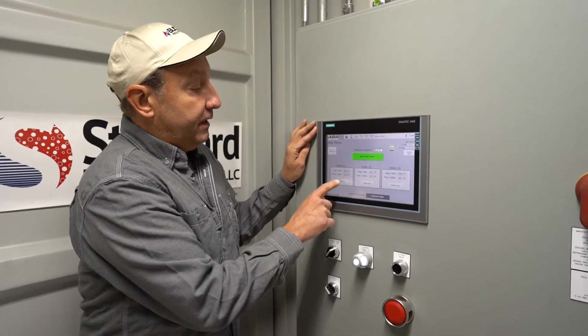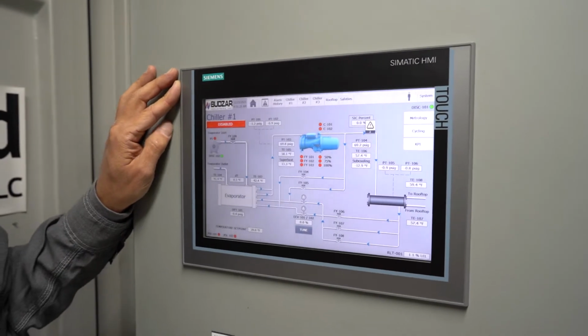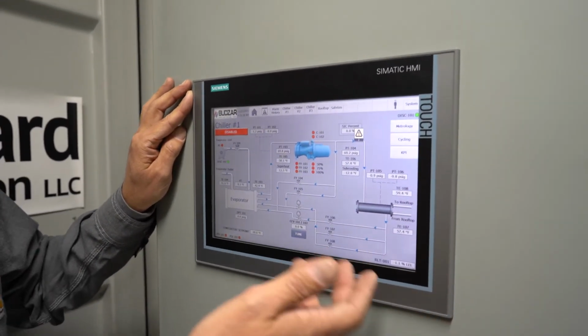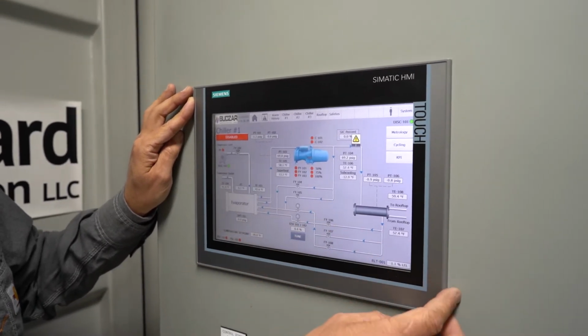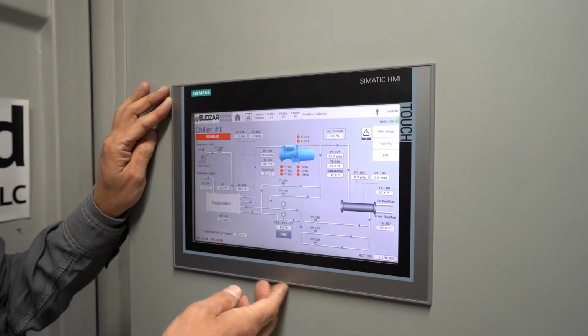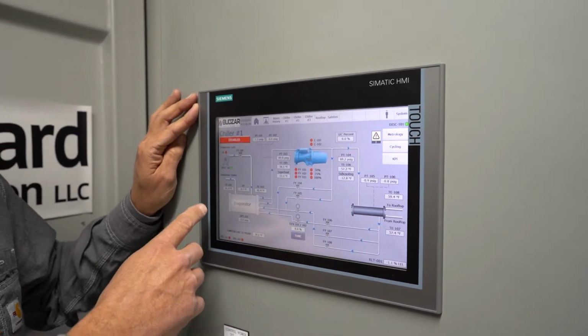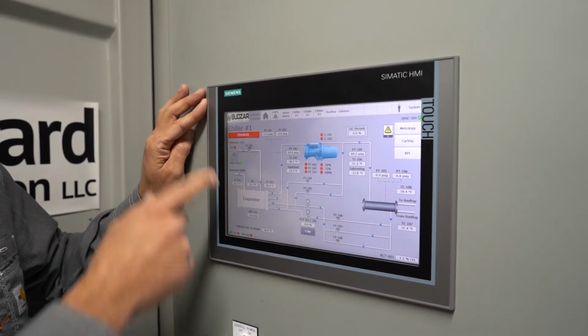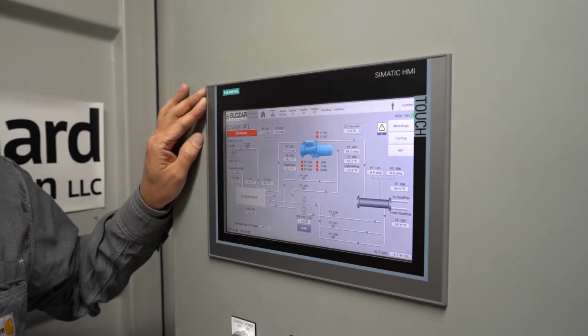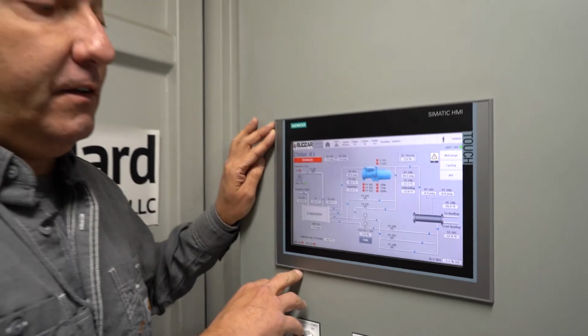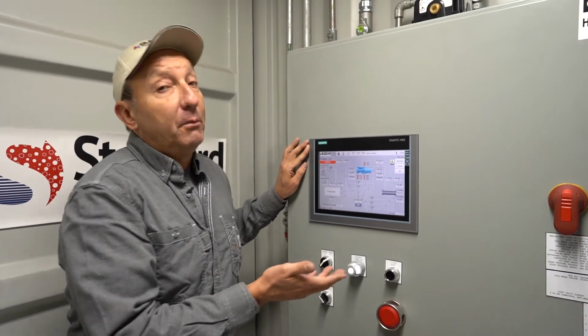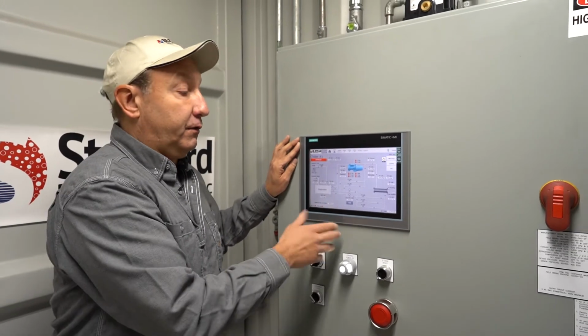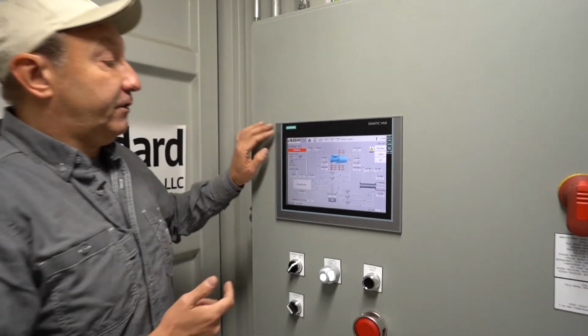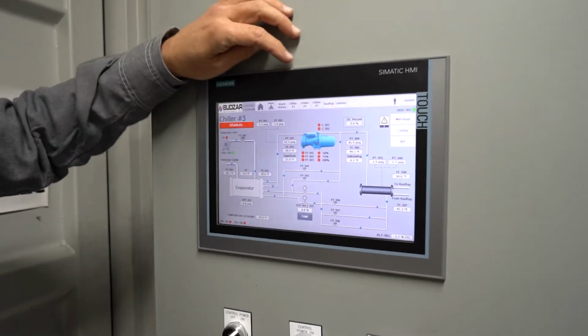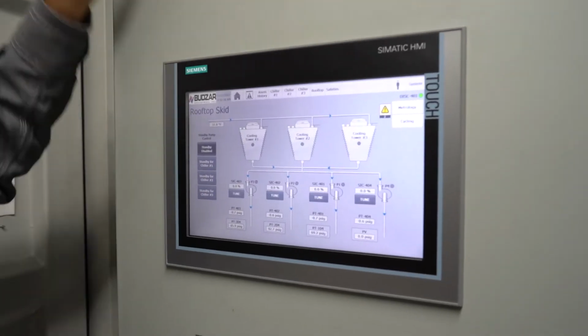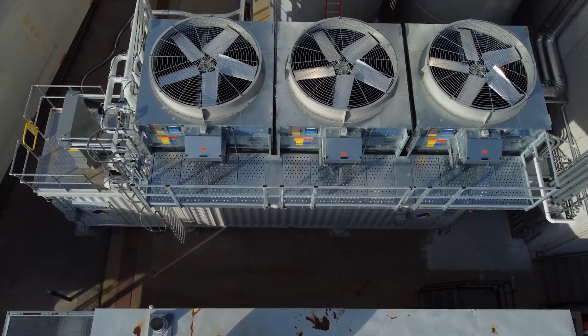We have 3 individual circuits. They can be displayed, and when the system is running, we turned it off so we could do the recording and the video, but you can see there's a lot of useful information on this screen. We can monitor superheat, subcooling, process temperatures, flow rates, the pump on, off, compressor on, off, whether it's loaded, unloaded. There's a lot of information on here that's great to just monitor the system and maintain good performance, or for troubleshooting purposes. If there was something wrong, or it's very useful information, and we could go to each circuit or each chiller. Now we're at chiller 2, chiller 3, and then we also have the rooftop system for the tower system. Again, we have 3 pumps, 1 for each chiller, and then a standby pump.